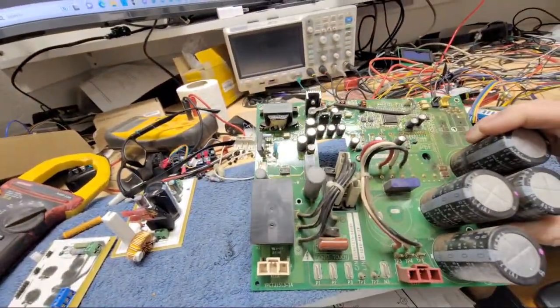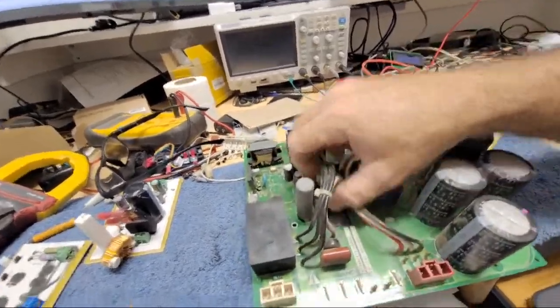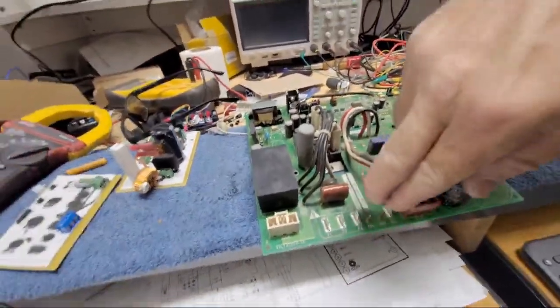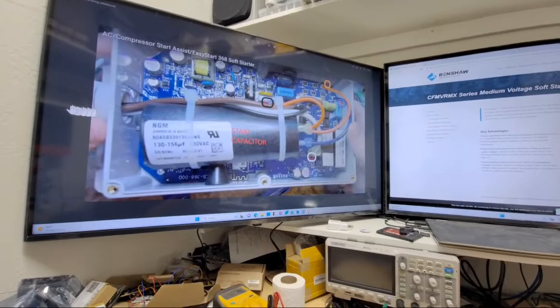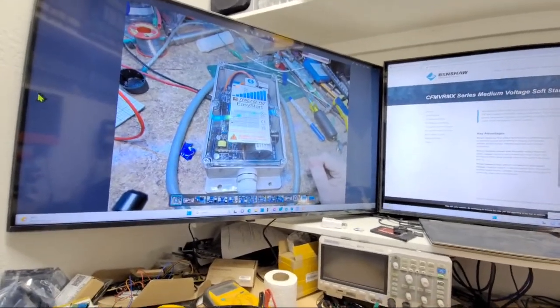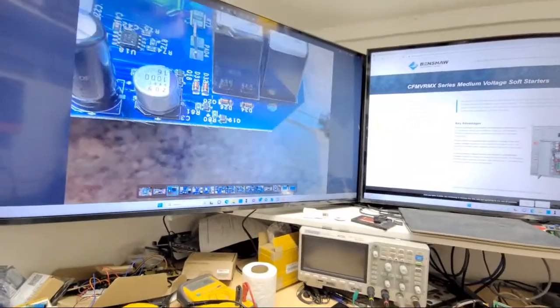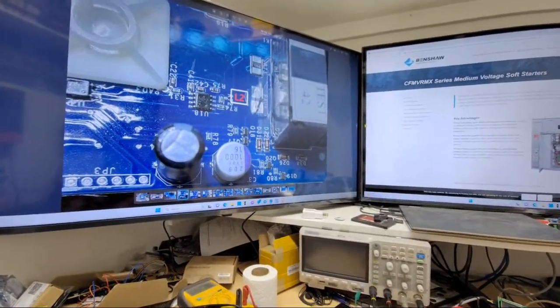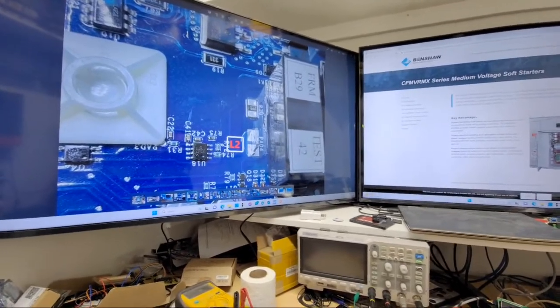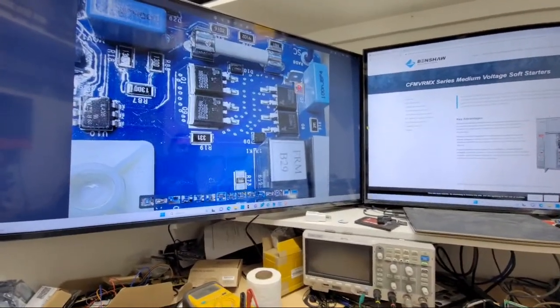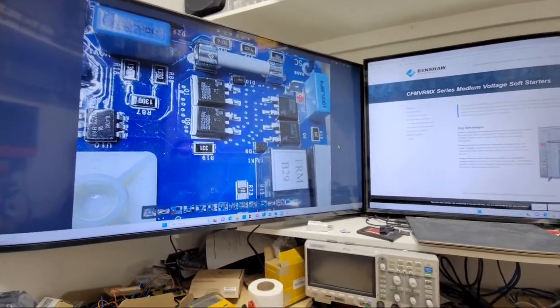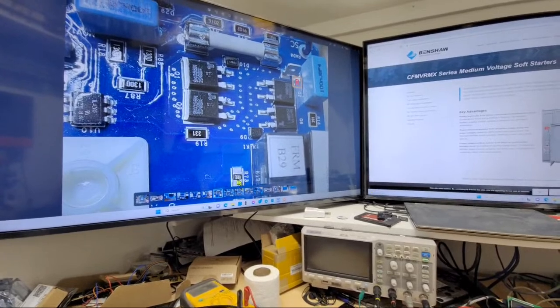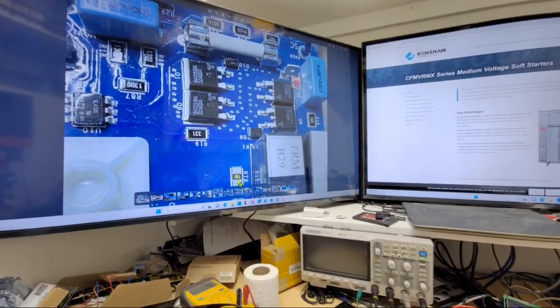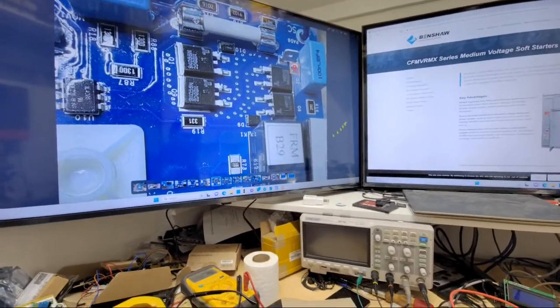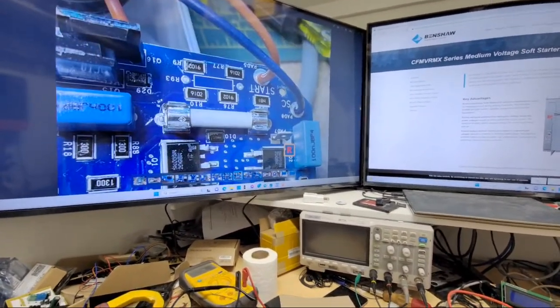If you look at any VFDs, IPMs, or VRF equipment, you'll see current sensors on at least two of the three legs. I don't think this has any of that. Something you could do is use shunts, which is what I might try doing - you put a shunt in, read the voltage drop across it with a microprocessor, run some math, and get an approximation. But I don't really see that kind of stuff in here. They do have this right here, which is probably a fractional ohm, and it's pretty massive. It almost looks like they're using this to shunt the relay right across the other potential down there. Kind of crazy.